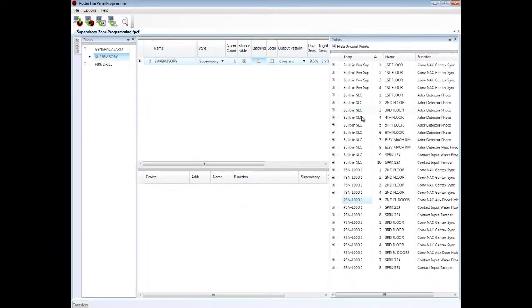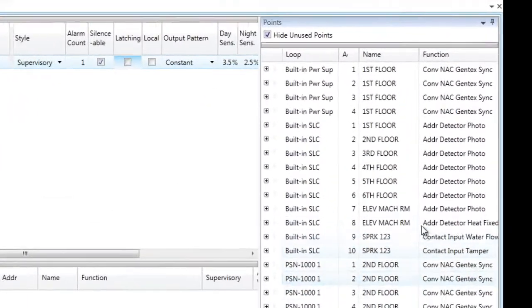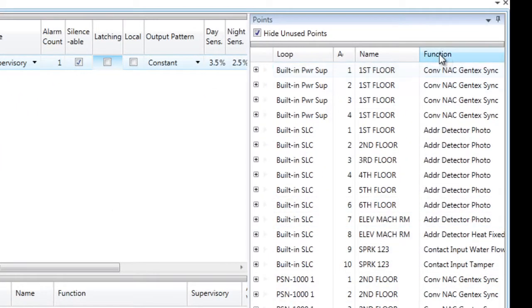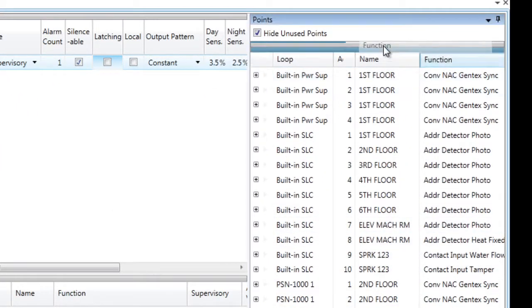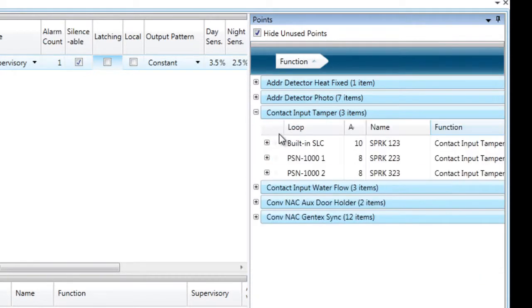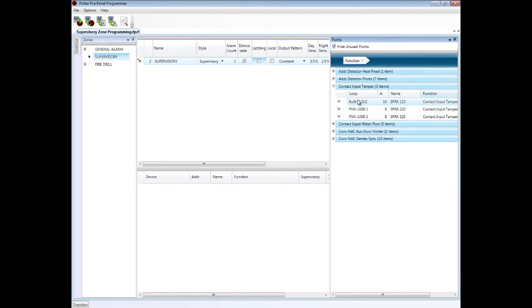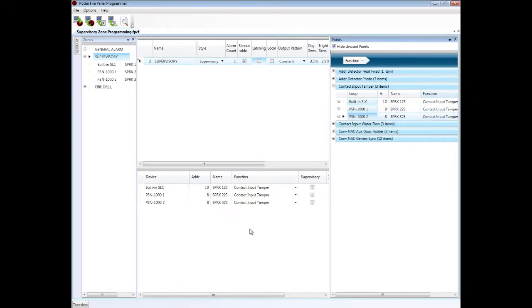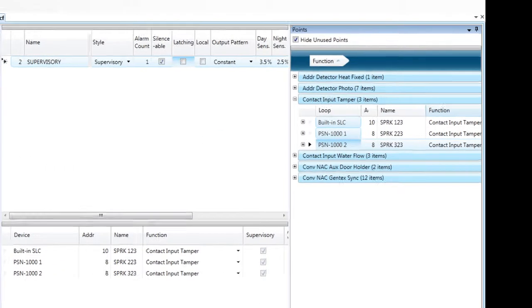And now I'd like to find those tamper points in my points list over here. So I'm going to filter by function, and I'm going to find my tampers, which are on my built-in SLC and my two power supplies. I'm going to select all three of those and assign them to the supervisory zone.